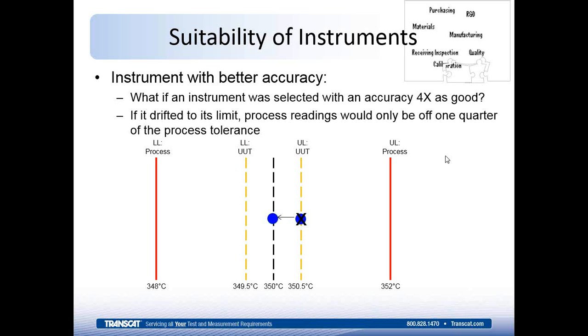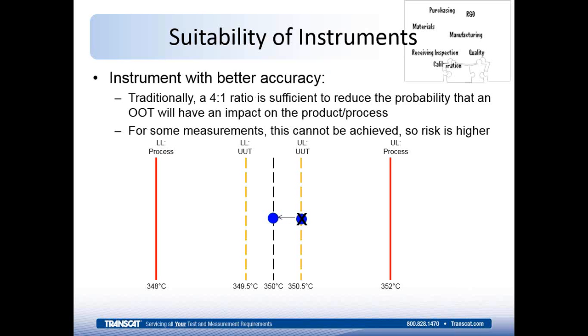So a 4-to-1 ratio is usually used, and if it drifts to its limit for the instrument being used, then only 1/4 of your process tolerance would be used up. And you're minimizing the number of bad process measurements by doing that. So again, if we took it to 10 times or 100 times better, there's limits of technology, there's increasing cost, and it gets to be too prohibitive to go too far with the concept. So traditionally, a 4-to-1 ratio is sufficient to reduce the probability of bad measurements, the probability of out of tolerance on the instrument being used, and reduces the impact on the process.